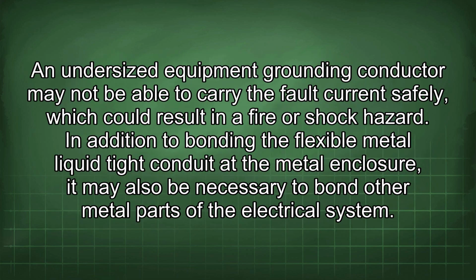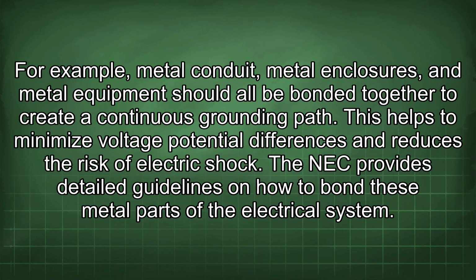An undersized equipment grounding conductor may not be able to carry the fault current safely, which could result in a fire or shock hazard. In addition to bonding the flexible metal liquid tight conduit at the metal enclosure, it may also be necessary to bond other metal parts of the electrical system. For example, metal conduit, metal enclosures, and metal equipment should all be bonded together to create a continuous grounding path. This helps to minimize voltage potential differences and reduces the risk of electric shock. The NEC provides detailed guidelines on how to bond these metal parts of the electrical system.